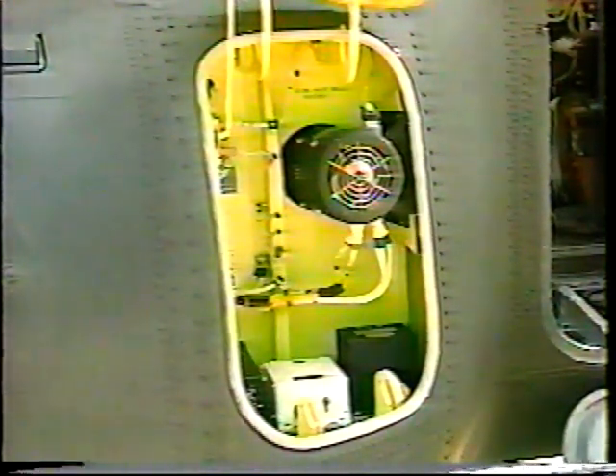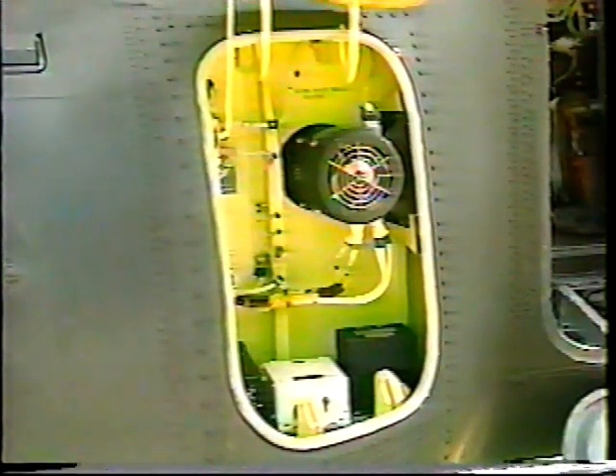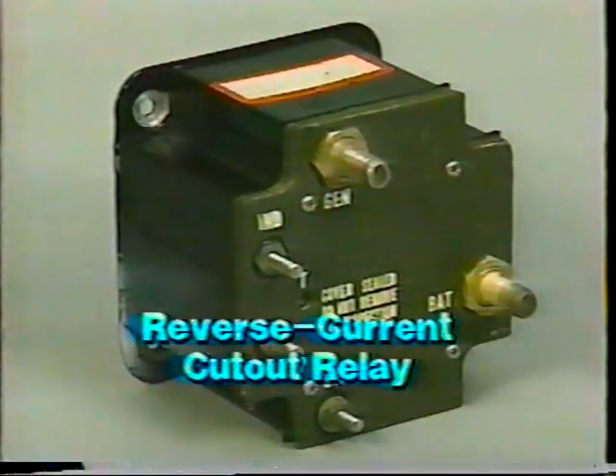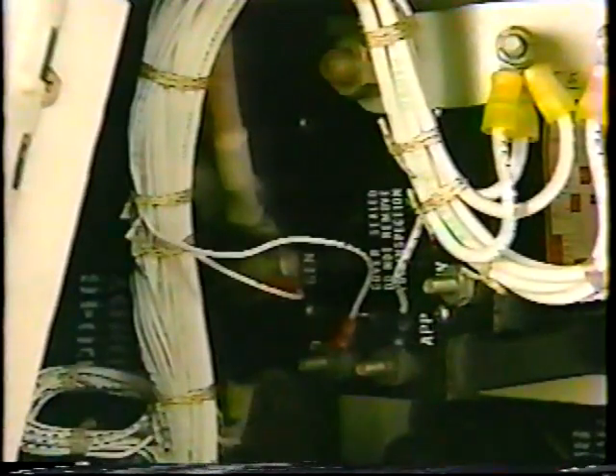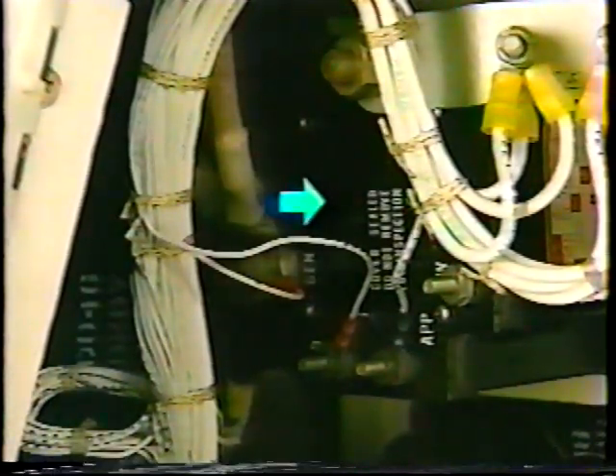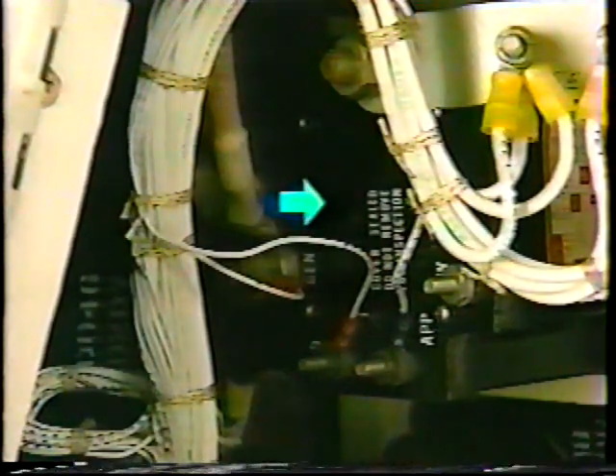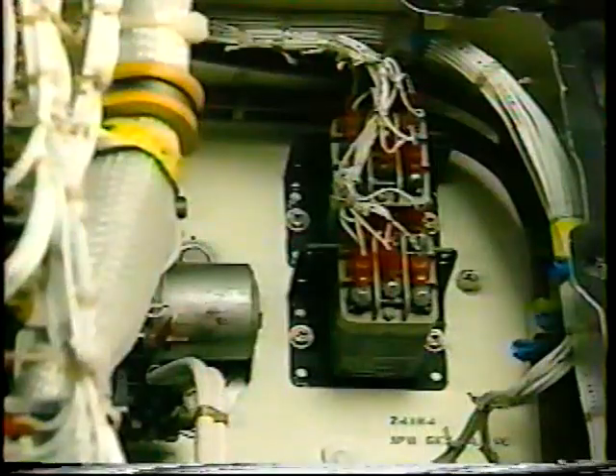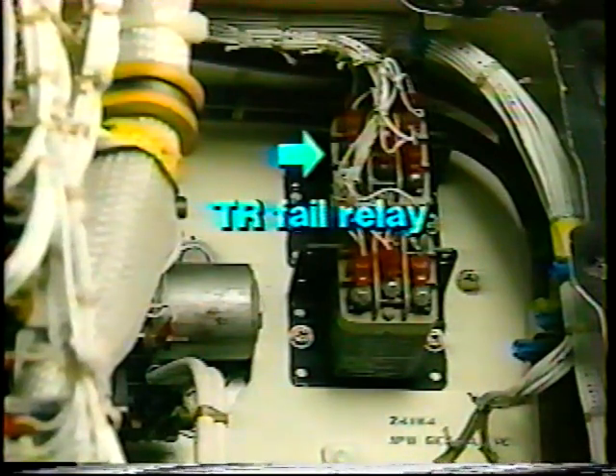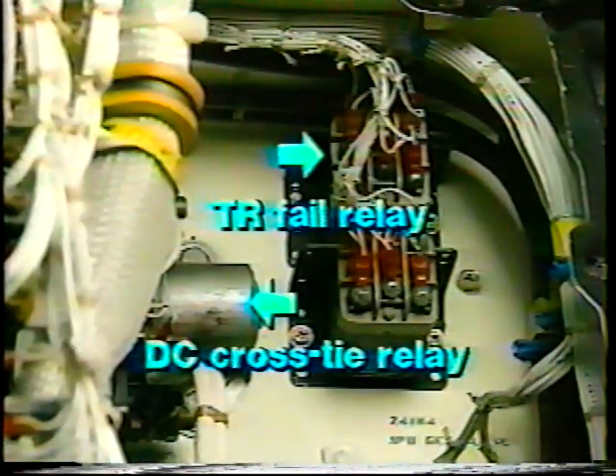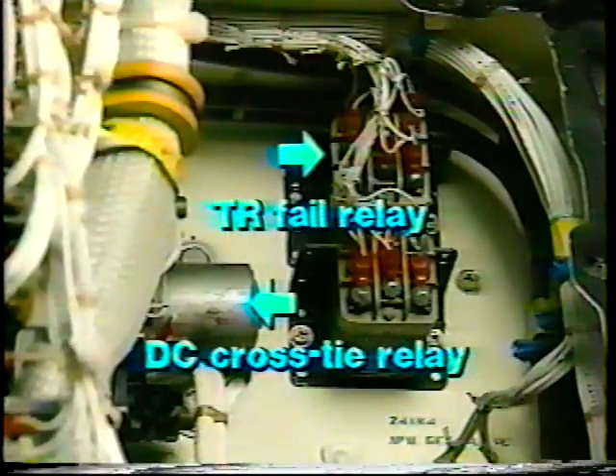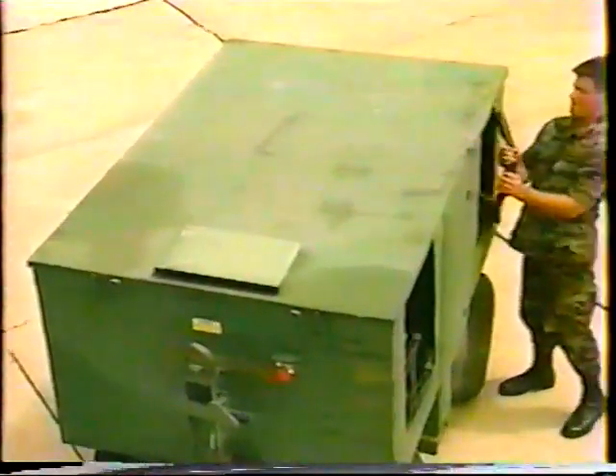To protect and control the TRUs, reverse current cutout relays are connected to the TRUs. As soon as the voltage coming from the TRU is greater than the voltage from the battery, the reverse current cutout relay, located in the PDPs, will connect the transformer rectifiers to the DC buses. If one of the TRUs should fail for any reason, the reverse current cutout relay will disconnect it from the bus and operate the appropriate TR fail relay, which in turn will operate the DC cross-tie relay to connect the 2 DC buses.